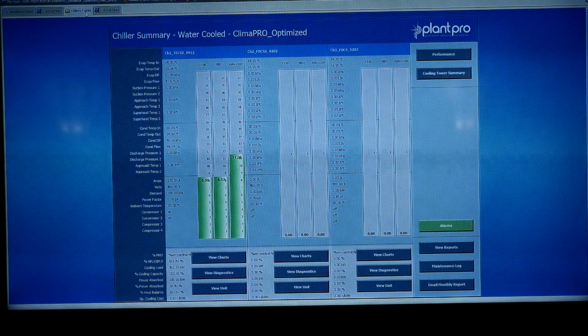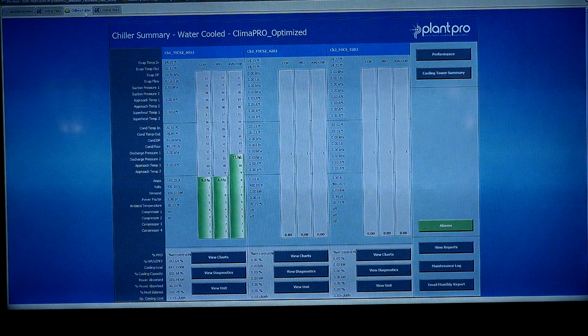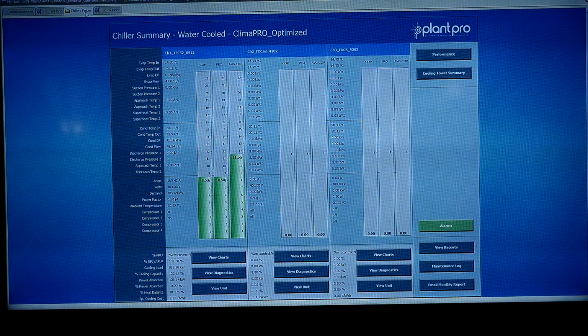You can see the three green bars in the middle, showing the performance of the machine. We have a unique calculation in PlantPro called Pro COP, or Pro kW per ton in the North American market. That lets us compare real-time performance with what the manufacturer states in their 4-point or 10-point study given to the mechanical contractor on site. We can go back to the client and say, looks like you might have a problem with your machine, we should run diagnostics or service it to drive efficiency back up.